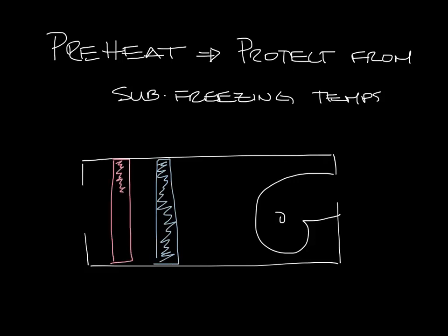So with preheat, you put the heating coil before the cooling coil. So this way, let's say if you have a 100% outdoor air unit and in the winter the air gets below freezing, you'll want to warm up that air using this preheat coil so that as the air goes across the cooling coil, you protect it from freezing and bursting the coil.